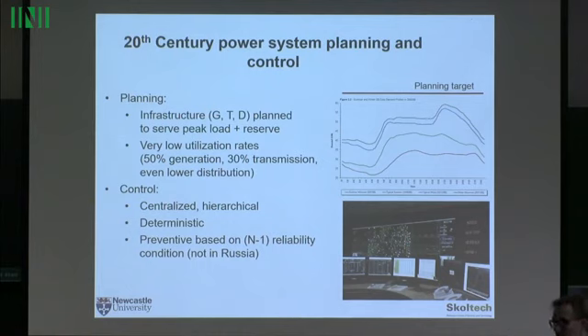So remember, N-1 is considered sacrosanct in the West, but it's not - you may achieve the same things using clever control, and Russians have been doing it forever because they had to. This is, I think, the way we are generally going, to get rid of these very low utilization rates - you can do things by control, but system operators hate it, because control may fail or be poorly designed, leading to failure. Whereas if you have a lot of fat, a lot of security margin, you will survive. It's far safer, but far more expensive.